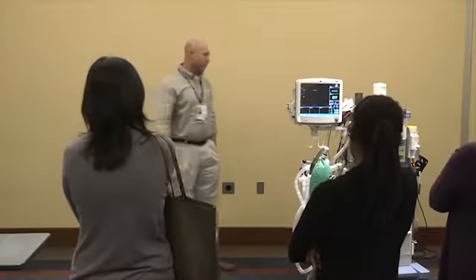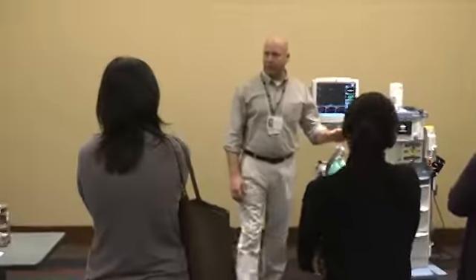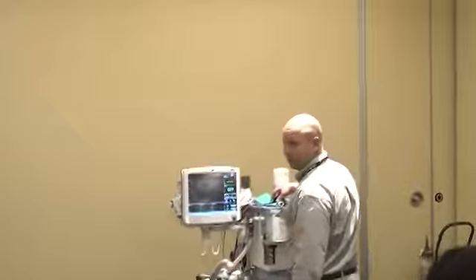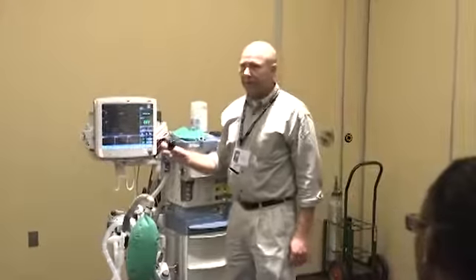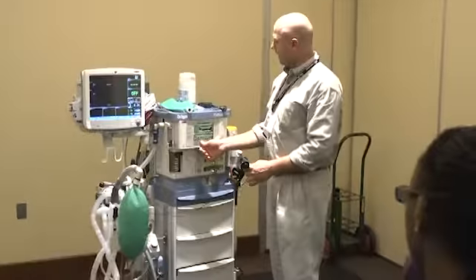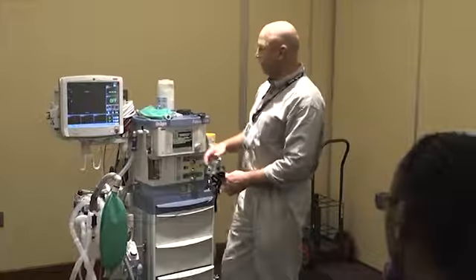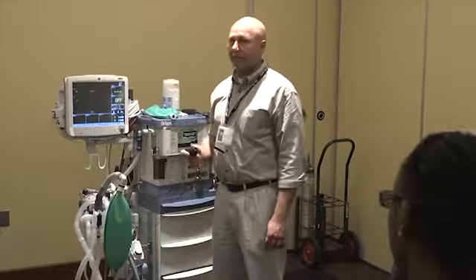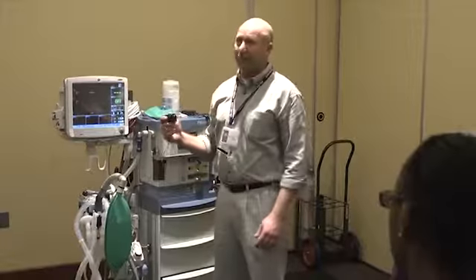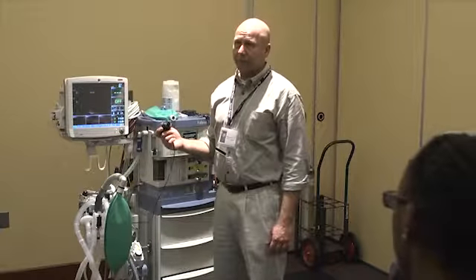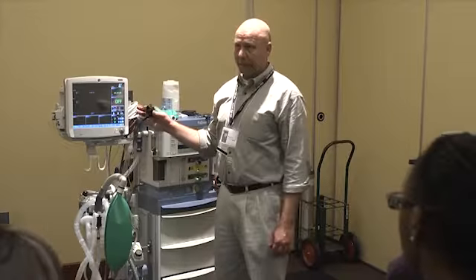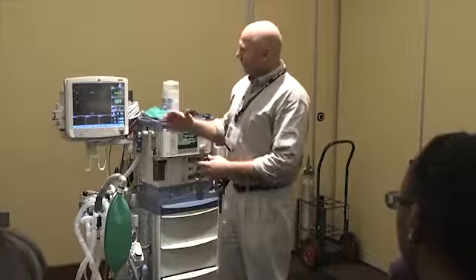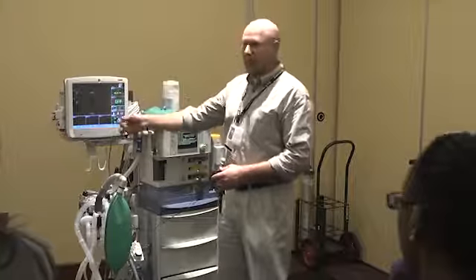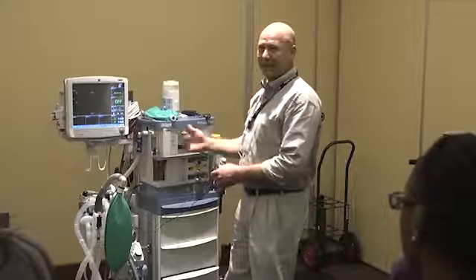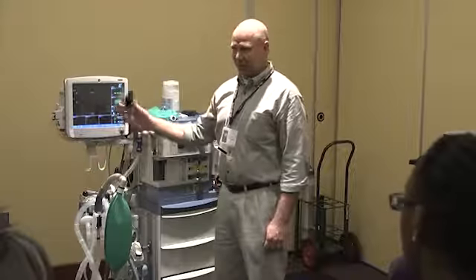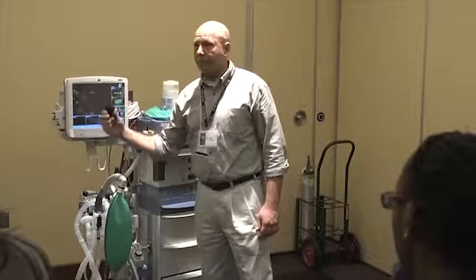Okay, as we go down, the very last protection before it comes to y'all is your O2 sensor. Now this O2 sensor, nice thing about the newer machines, they tell you, remove O2 sensor and expose to room air for 2 minutes. It's the same for the Narkomeds, but they don't tell you that. Really, 2 minutes. It needs to be done for 2 minutes. You've got to let it cool to ambient. Otherwise, your readings will be a little off. Nowadays, it's not so much of an issue because you've got your backup O2 reading here. And very few of y'all even pay attention to the one on the machine, because you're always looking at your monitors. But 2 minutes.